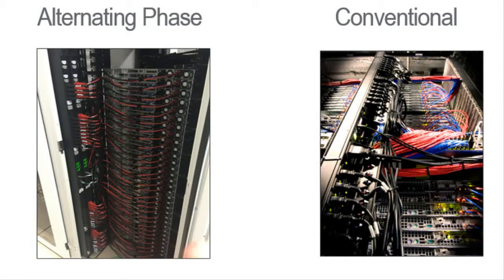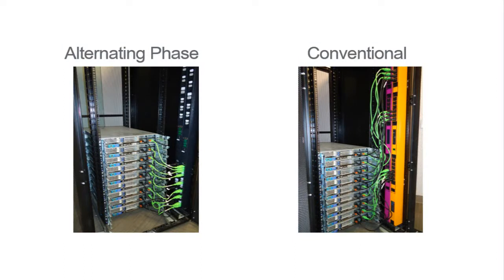Here's a closer look at real-life photos of fully populated racks. The cables on the conventional PDU on the right run up and down the rack, requiring multiple cable lengths, which can disrupt airflow. As equipment is added over time, the cabling becomes more disorganized and chaotic, leading to reduced airflow and higher power usage effectiveness, or PUE. On the left, the alternating-phase PDU supplies the equipment with uniform-length cords running straight across to the equipment, with good airflow. Which rack would you rather have in your data center?